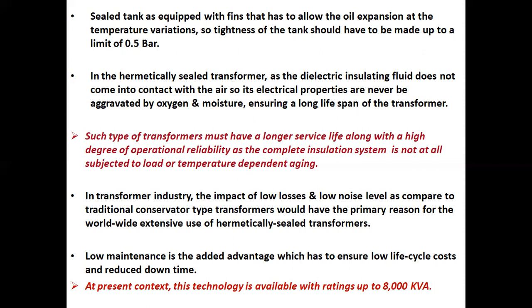In the transformer industry, low losses and a low noise level as compared to traditional conservator type transformers are the primary reasons for the worldwide extensive use of hermetically sealed transformers. Low maintenance is an added advantage, which ensures low life cycle costs and reduced downtime. At present, this technology is available with ratings up to 8000 kVA.